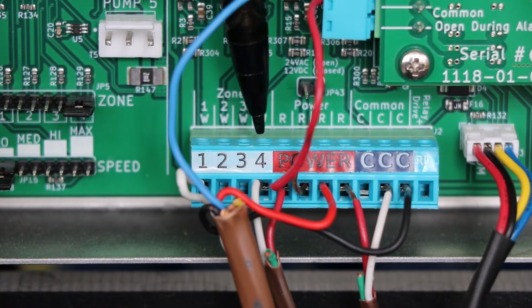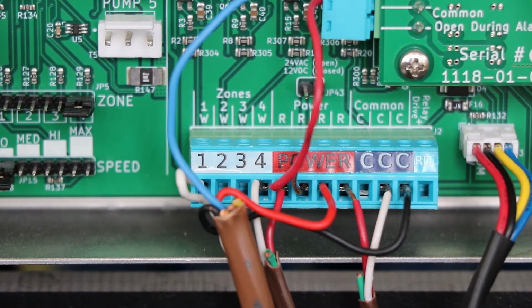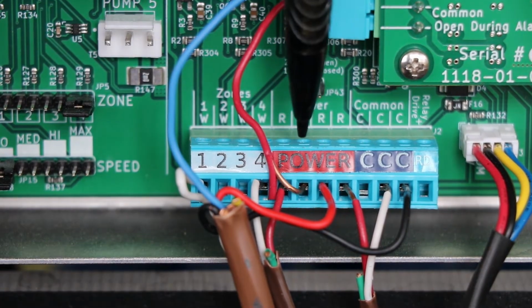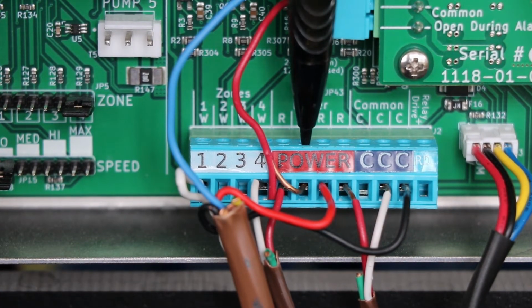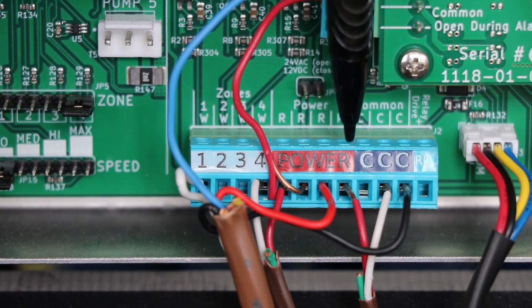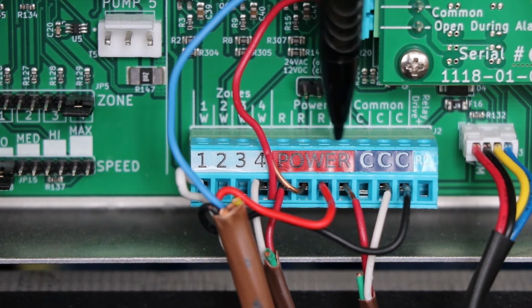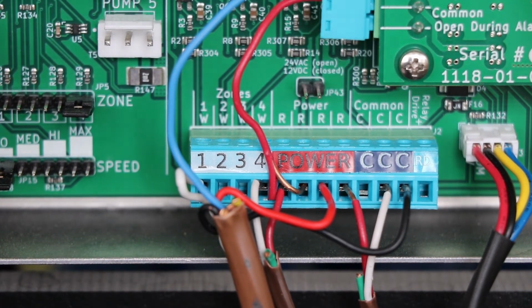Connect the white wire to the thermostat zone you wish to connect it to. The red wire goes into the power terminal R. Then, the black or blue line goes into a common terminal. Do not plug the 24 VAC power supply into the outlet until it is time to power up.